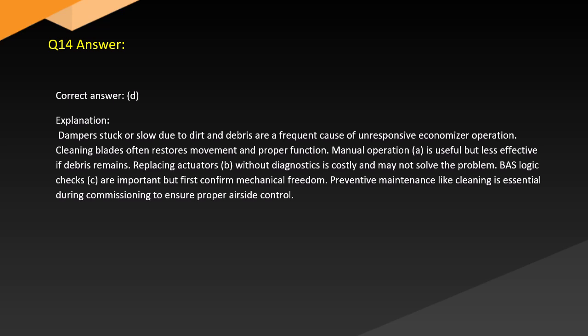Answer. Correct answer. D. Explanation. Dampers stuck or slow due to dirt and debris are a frequent cause of unresponsive economizer operation. Cleaning blades often restores movement and proper function. Manual operation, A, is useful but less effective if debris remains. Replacing actuators, B, without diagnostics is costly and may not solve the problem. BAS logic checks, C, are important but first confirm mechanical freedom. Preventive maintenance like cleaning is essential during commissioning to ensure proper airside control.